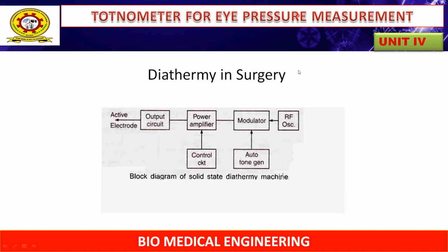In this figure, the RF generator provides a high frequency carrier signal, which is modulated by a tone generator, giving the waveforms for the coagulation and cutting methods. The RF power is tuned by a control circuit operated by the surgeon. The output circuit couples the modulated RF output to the active electrode. In this way, the solid state diathermy machine gives proper therapy. Let us look at a video clip on this content.